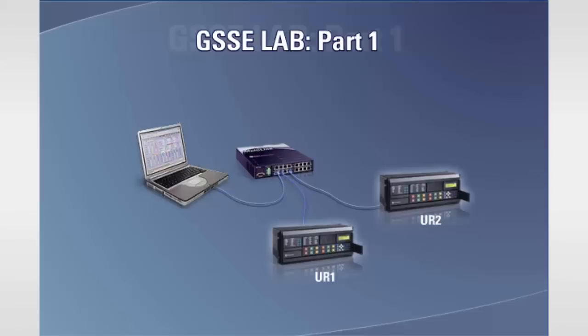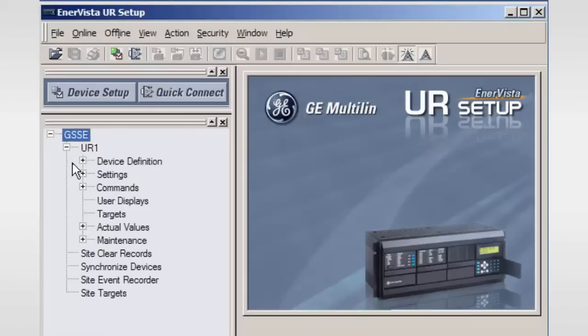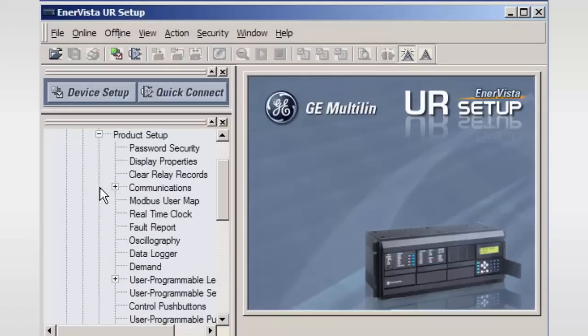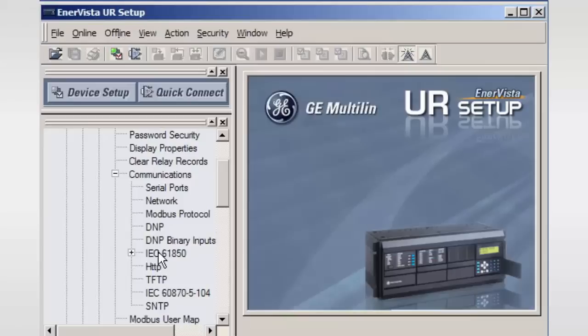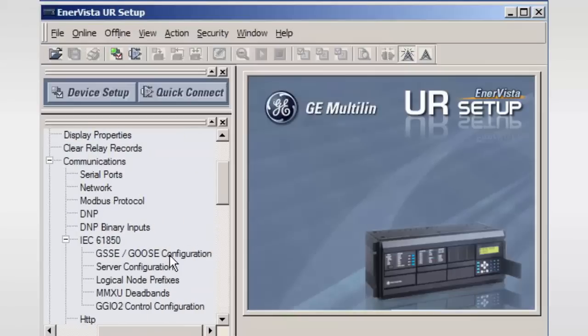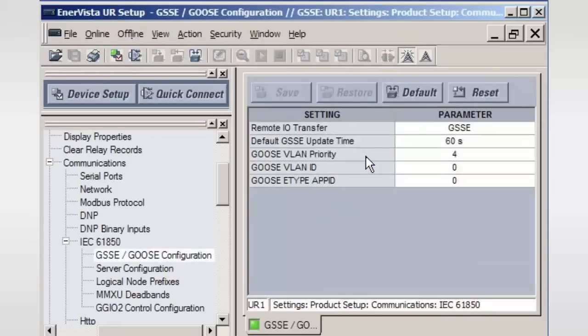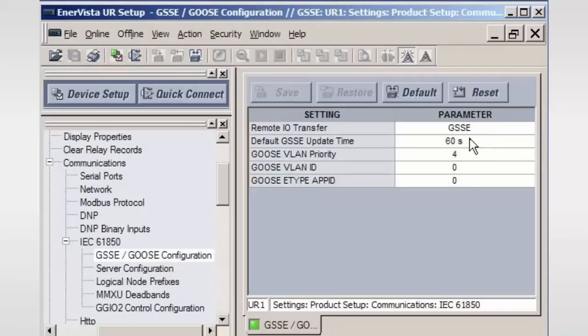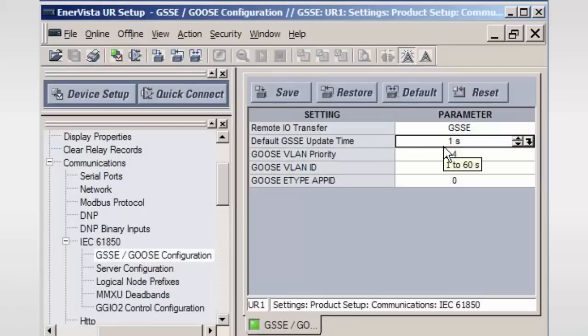Launch the EnerVista UR setup software. From the Settings menu, select the Product Setup menu, then open the Communications menu. Within the Communications menu, select the IEC 61850 configuration menu, and then the GSSE/GOOSE Settings menu. Set the Remote I/O Transfer to GSSE. The default GSSE update time sets the maximum desired elapsed time between GSSE remote output multicast messages — the range is between 1 to 60 seconds. For the lab exercise, this should be set to 1 second. This setting will also be sent as part of each GSSE remote output multicast message, as it is used by receiving relays to determine if the transmitting relay is still communicating. Each multicast message must contain a 1 to 20 character name of the sending device. Open the Setup menu, then the Installation sub-menu, and enter the name 'UR1' in lowercase.